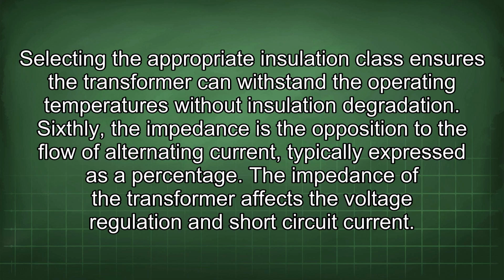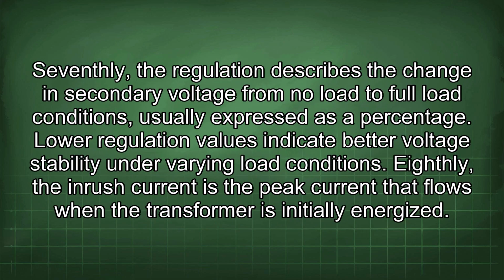Sixthly, the impedance is the opposition to the flow of alternating current, typically expressed as a percentage. The impedance of the transformer affects the voltage regulation and short-circuit current. Seventhly, the regulation describes the change in secondary voltage from no load to full load conditions, usually expressed as a percentage. Lower regulation values indicate better voltage stability under varying load conditions.